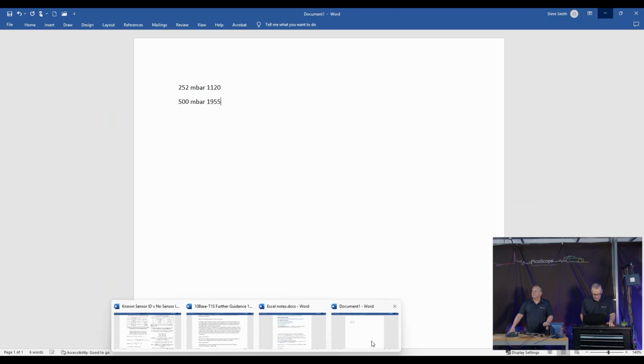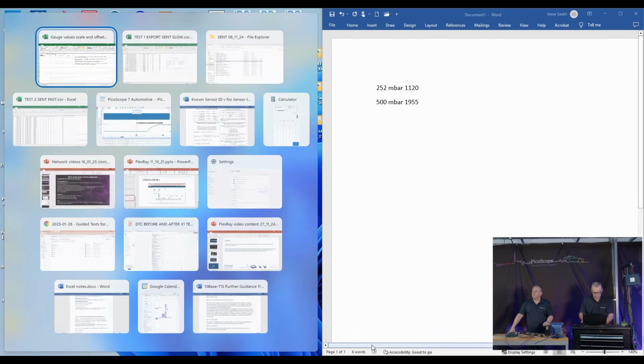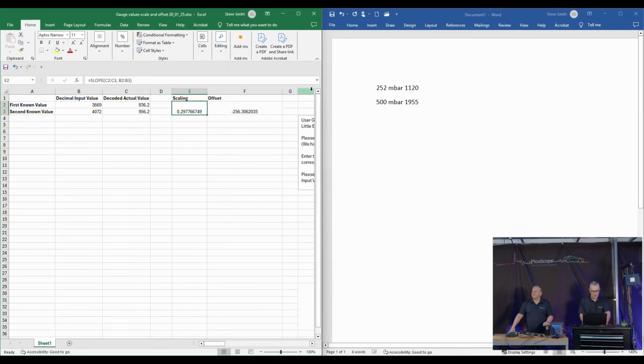We use the values that we got. First of all, we want our decimal input value and decoded actual value. This is the physical pressure value that we've measured: it was 252 millibar, and the encoded value is 1120. Here the actual pressure value was 500 millibar, and the encoded value there was 1955. Enter. So that's given us the scale and the offset we can apply to those coded values we got in channel 1 from PicoScope.